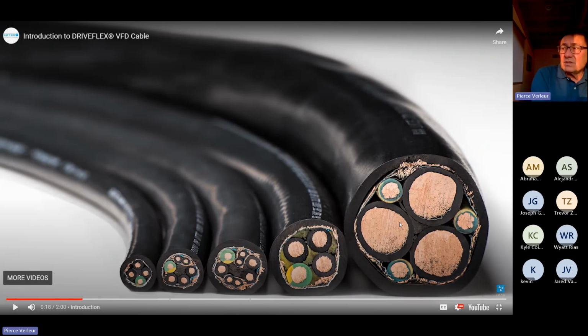Why wouldn't we just use this? Well, of course, it's cost. These cables can be, and this is where I would have loved to have Chris Keller because he knows the costing on these things, but I'm going to estimate that these cable costs are going to be 1.2 to 1.5 times the cost of normal cable, which, by the way, if you have a problem and you delay your installation by a day or two because you can't solve the problem, and I'll talk about the trip I made to Mexico in a second, then that cost is immediately justified.